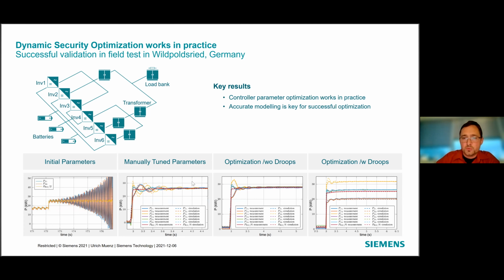Now, what we did afterwards was run our optimization on this model. You can see two examples: one where we allow changing the droop parameters, which impacts the steady state, and one where we keep the droop parameters constant. When you optimize droop parameters, the steady state—the sharing of the load step among the 6 inverters—is not equal anymore, but there are hardly any oscillations. If you fix the droop parameters and only tune the time constants, you can still improve significantly over the manually tuned system.